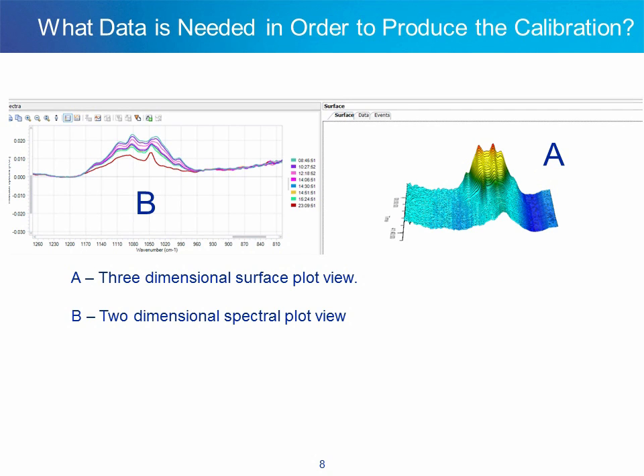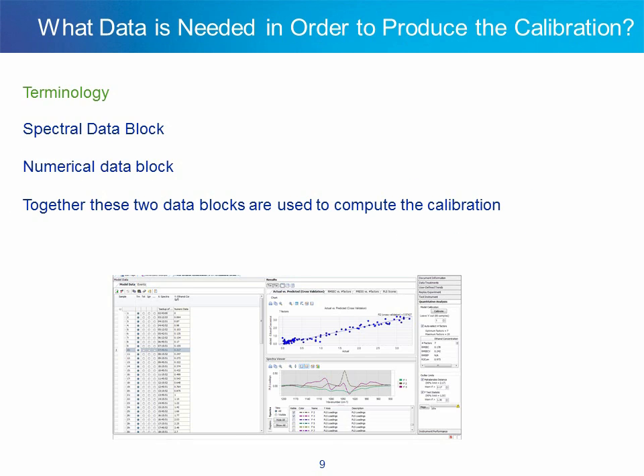Here is an example of data used to develop a calibration. Plot A is a three-dimensional surface plot, reversed with respect to time, showing a fermentation. Plot B shows some of the spectral data in a two-dimensional format. The spectral data block is absorbance data plotted against wave number. The numerical data block comes from either an offline technique or from samples that were weighed out. Together these two data blocks are used to compute the calibration.